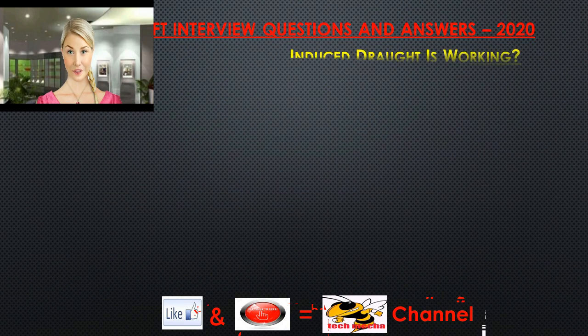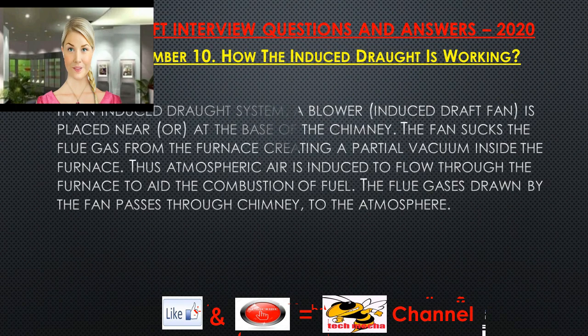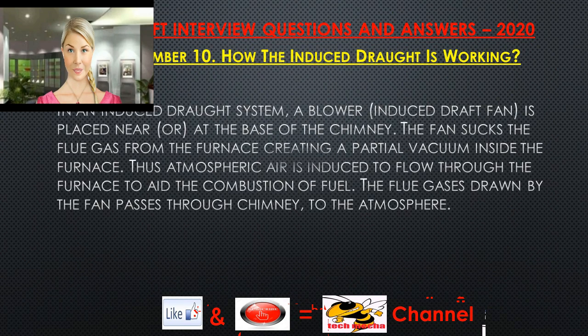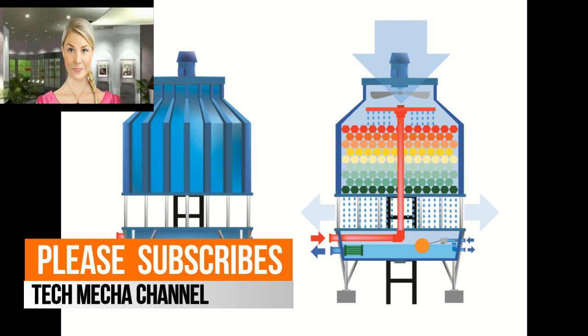Question 10: How does the induced draft system work? In an induced draft system, a blower or induced draft fan is placed near or at the base of the chimney. The fan sucks the flue gas from the furnace, creating a partial vacuum inside the furnace. Thus atmospheric air is induced to flow through the furnace to aid combustion, and the flue gas drawn by the fan passes through the chimney to the atmosphere.